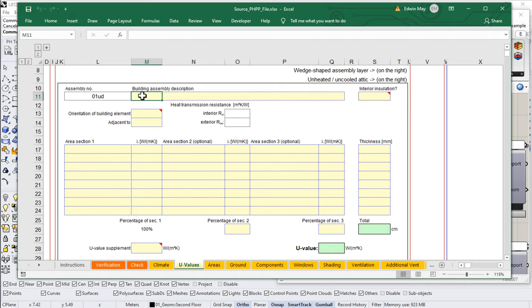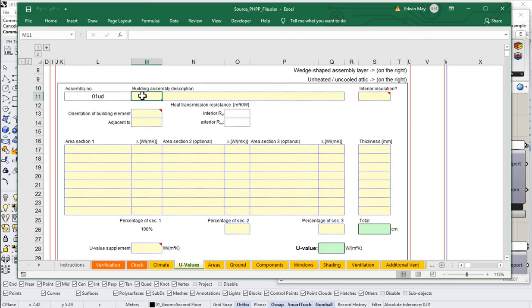So I'm just going to use it as a little side tool. I could go off and do this in any sort of numeric constructor, follow the ASHRAE Handbook of Fundamentals chapter, what chapter 25, chapter 27 procedures, to calculate your U values or ISO 6946. You just follow those procedures. I'm going to use this little calculator, which is built into PHPP. So in the U values page, built into PHPP here.